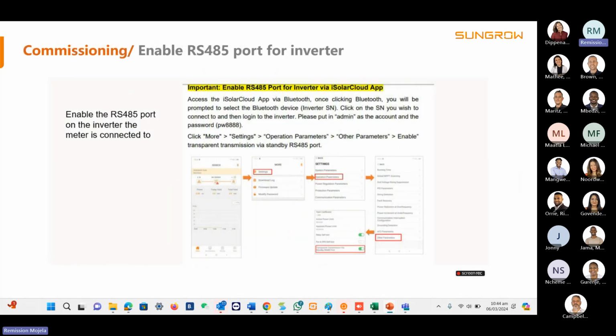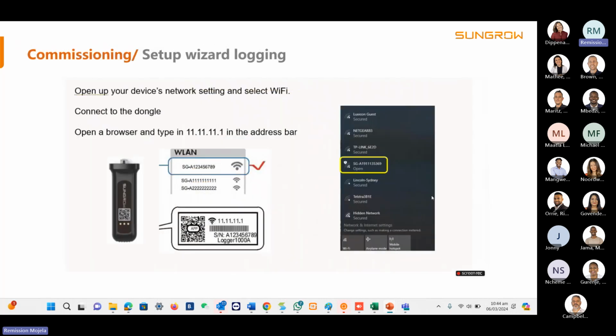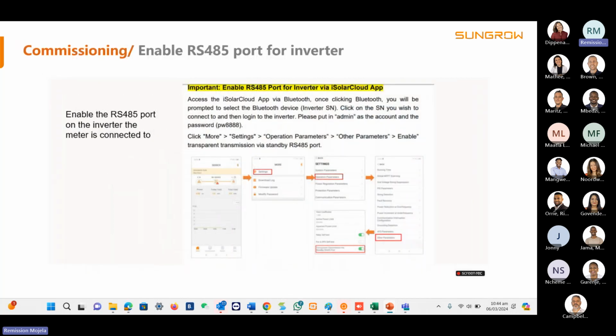And to add the meter, you just have to enable the transparent transmission via standby port, which is a setting on the inverter directly, and then after that you add the meter. The standard Modbus number for the meter is always 254, which we normally assist clients with when they are on site doing their first commissioning. If ever you need assistance, you just have to give us a call. We'll be able to explain this more when you're on site as well.